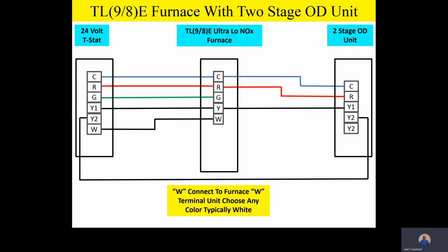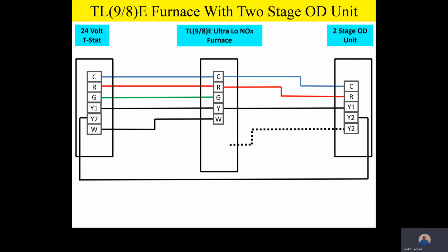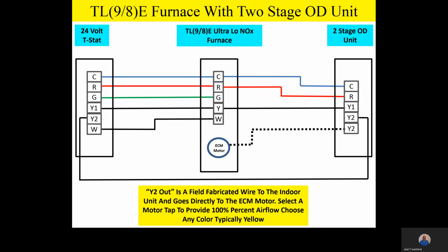Now, team, please watch this. Outside on the control board, outside on the two-stage unit, there's going to be a Y2 output, a Y2 out. That Y2 out is going to be a field fabricated wire, a field fabricated 24-volt wire, and that Y2 out on the outdoor control is going to come in, and you're going to select a motor speed tap on the ECM motor to give you 100% cooling airflow. And again, select any color you like, but most contractors are going to use that yellow wire outside.